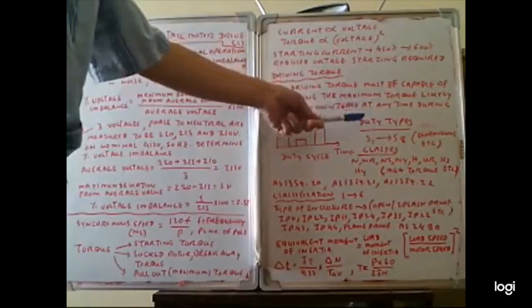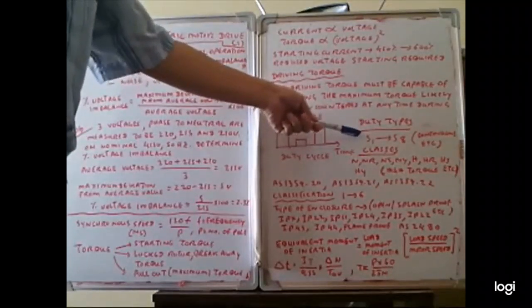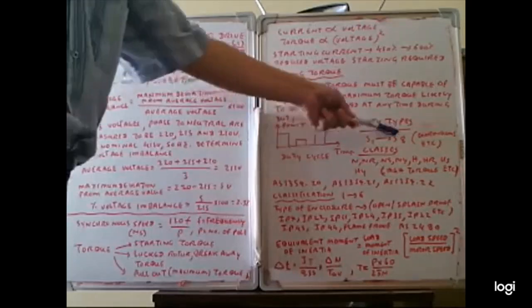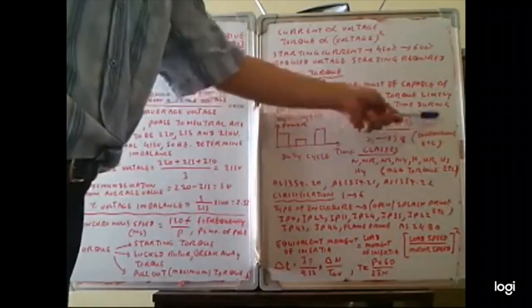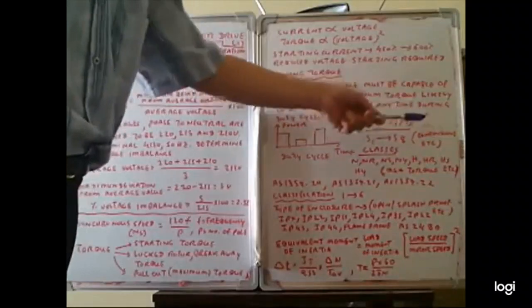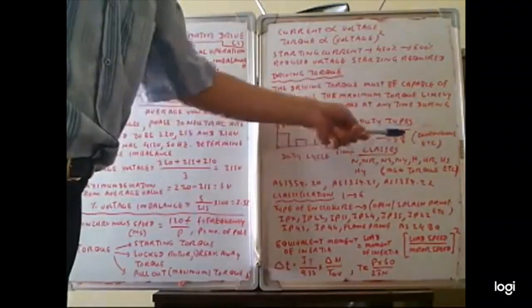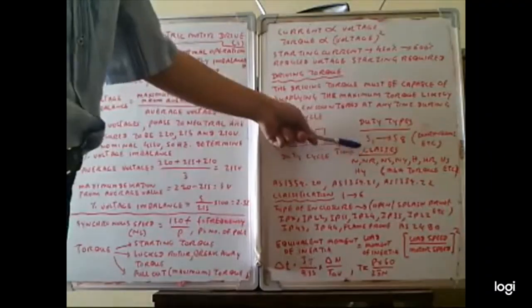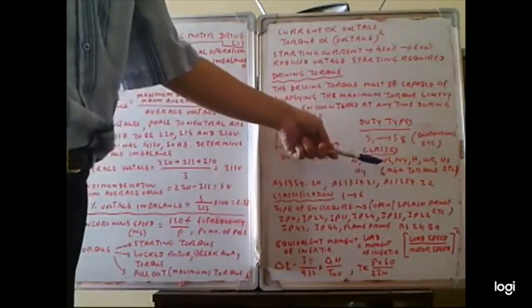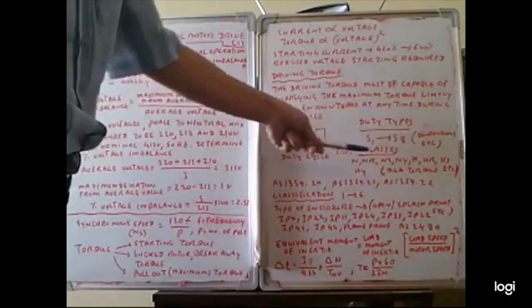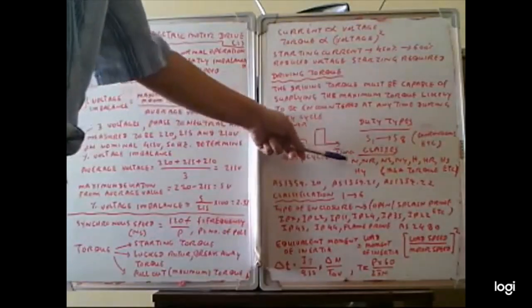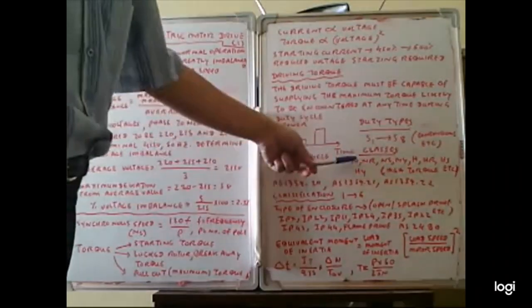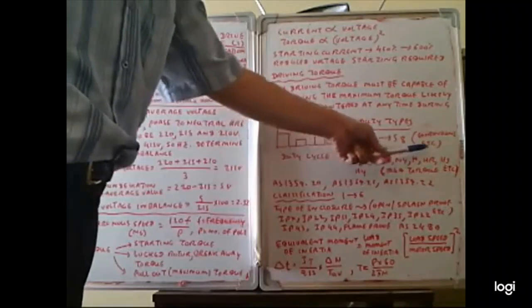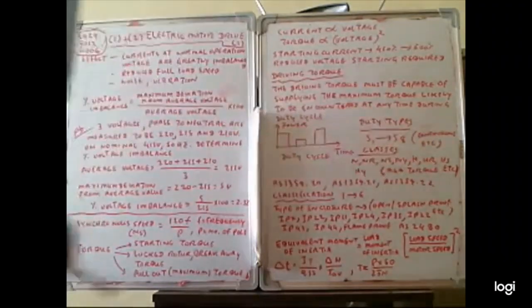Depending on the kind of duty cycle and the type, we can classify. Motor duty types can be classified from S1 to S8. For example, some motors are running continuously, some motors are running intermittently. Those things are determined by the duty types. And for motor classes, some motors require a high starting torque, some require a low starting torque. Which motor requires high starting torque and which requires low can be determined by the motor classification. The motor classification can be N, NR, NS, NY, H, HR, HS, and HY.